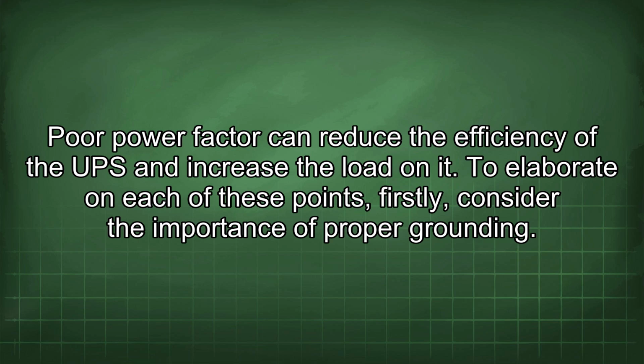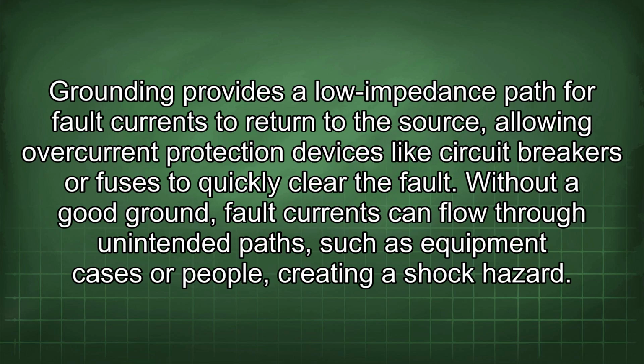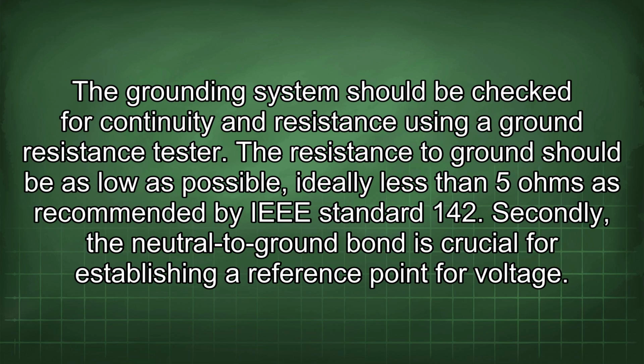To elaborate on each of these points, firstly, consider the importance of proper grounding. Grounding provides a low impedance path for fault currents to return to the source, allowing overcurrent protection devices like circuit breakers or fuses to quickly clear the faults. Without a good ground, fault currents can flow through unintended paths such as equipment cases or people, creating a shock hazard. The grounding system should be checked for continuity and resistance using a ground resistance tester.